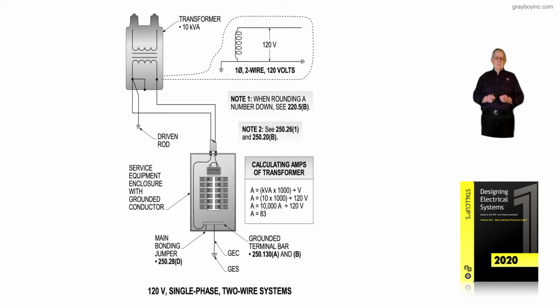But many times I get the question, why two tables? Well, Table 250.66 deals with sizing the grounding electrode conductor. This confused people. So they provided a new table, 250.102(C)(1), that lists the supply side bonding jumper, the main bonding jumper, the equipment bonding jumper on the supply side, and so forth. In other words, the terms and items listed at the top of the table reflect to the user exactly what the table provides the designer, installer, or maintainer to select the size of the conductors, based upon grounding electrode conductor or supply side bonding jumper, main bonding jumper, and so forth. Those items are listed in each table.